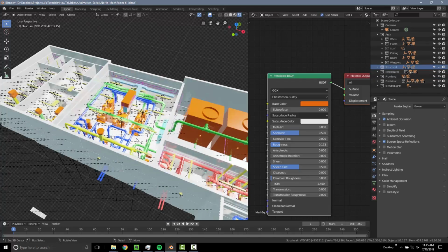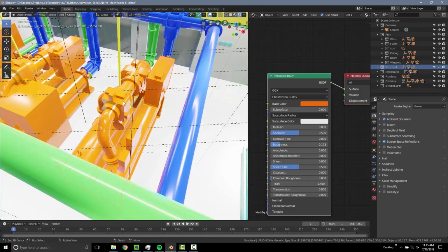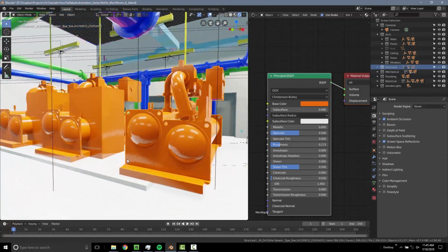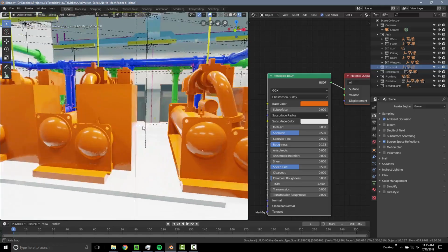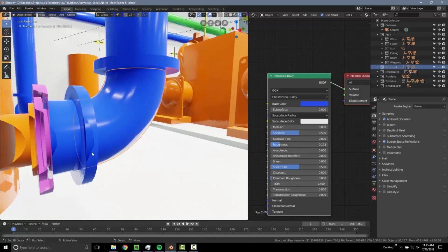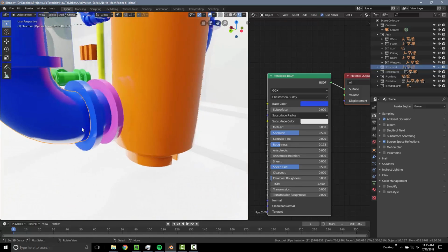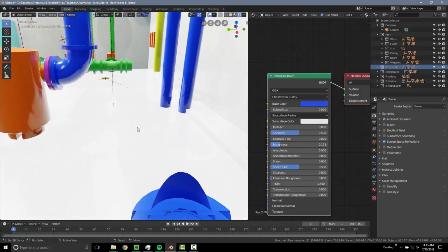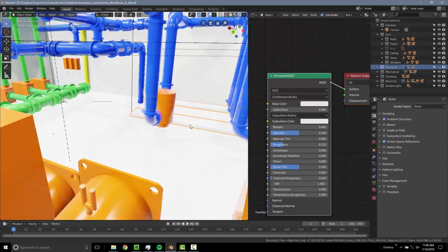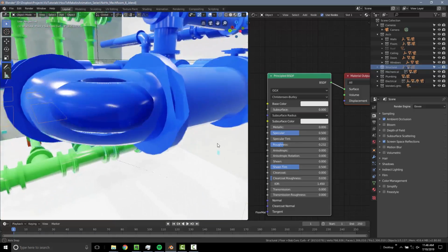So I'm just going to go through and I'm going to start looking at things. And right away, I'm going to notice that the housekeeping pad isn't aligned with the chillers. Maybe the chillers grew or something like that. So if that's something we want to fix, take note of that. Turn around over here. Looks like there's some housekeeping pads here that aren't really lining up to anything.